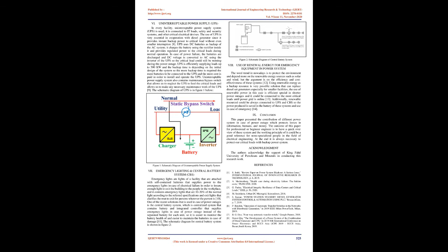UPS efficiently supplies loads up to 500 kilowatts, and the backup time depends on the initial design of the system, so the more backup time is required, the more batteries must be connected to the UPS and the more cost is paid to install and operate it. The UPS system also contains a maintenance bypass switch that allows us to bypass the UPS in feeding the critical loads and make any necessary maintenance work on the UPS. The schematic diagram of the UPS is in figure 1 below.